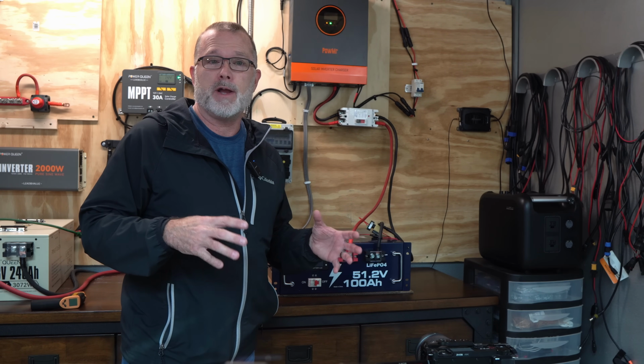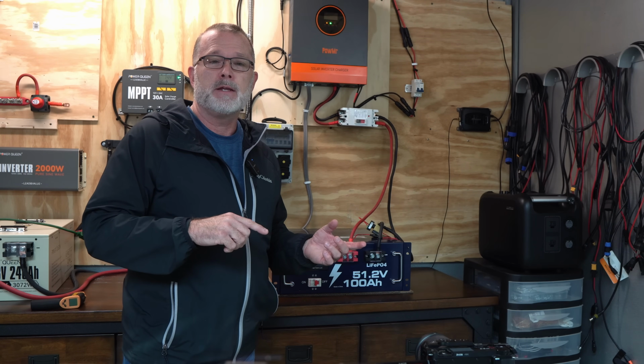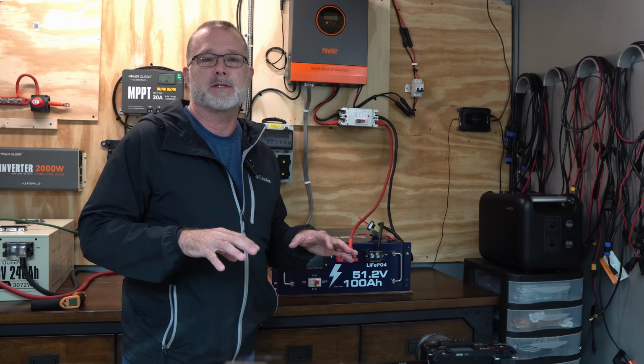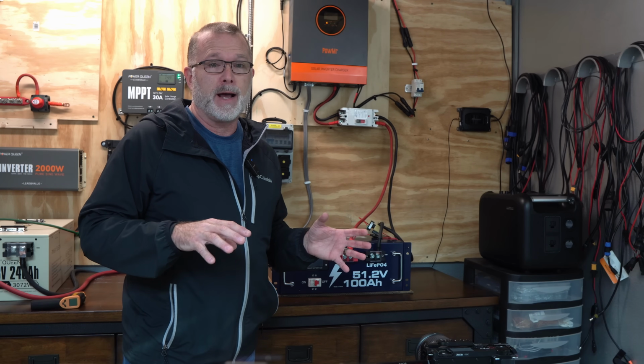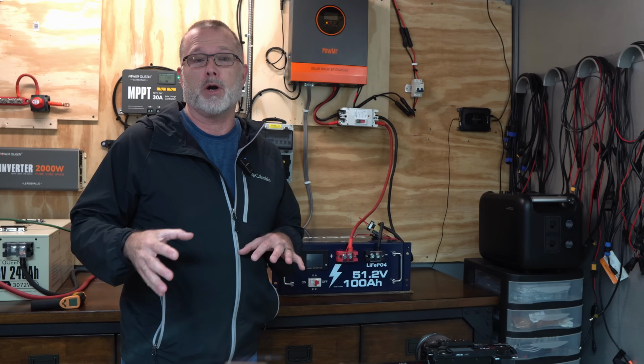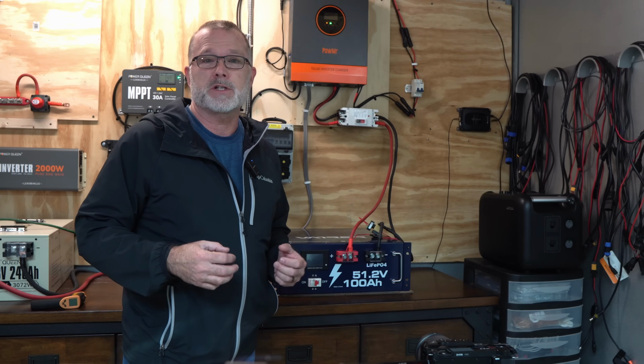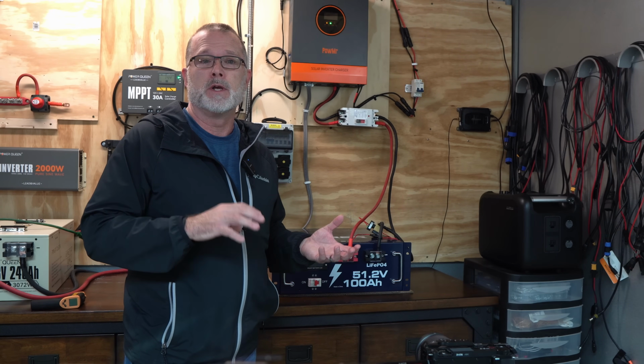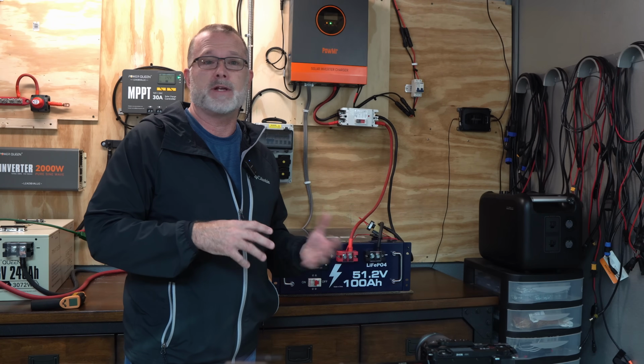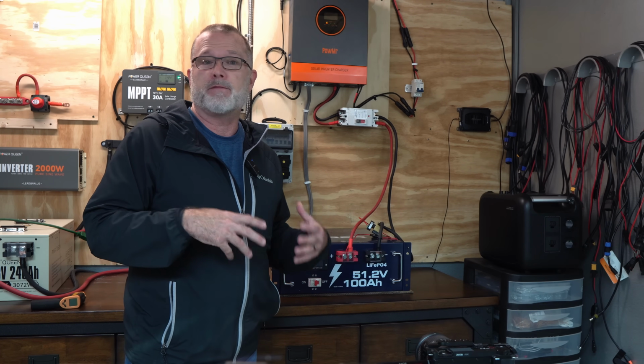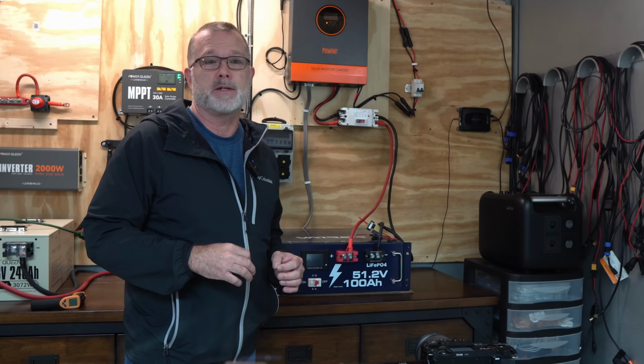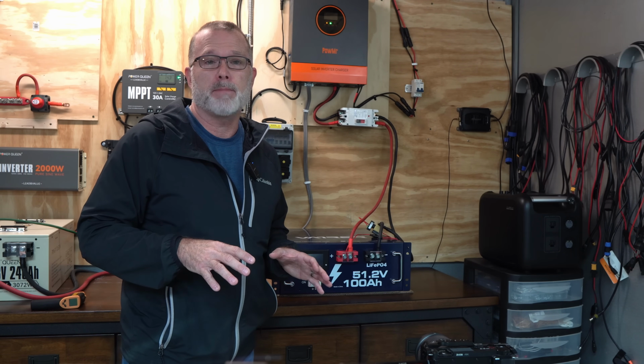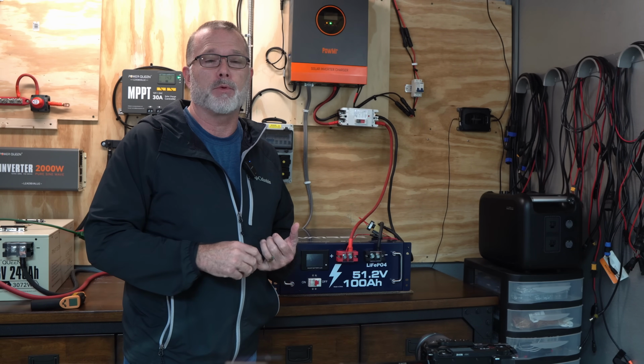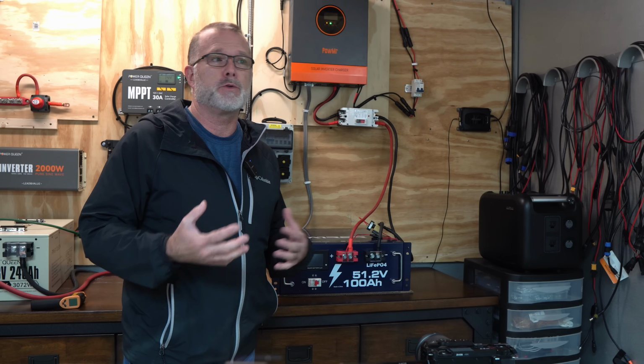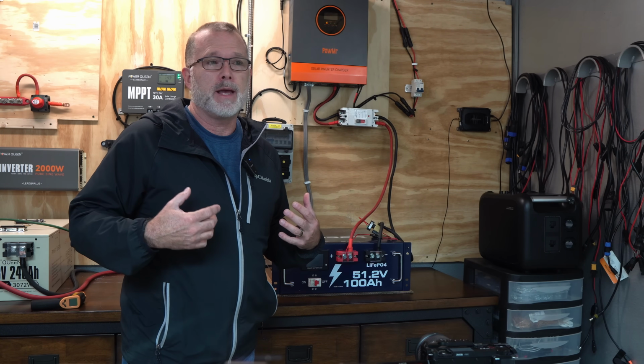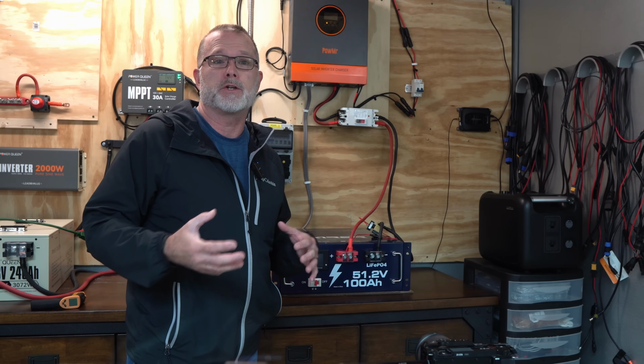In contrast, when you have multiple batteries connected in series, that natural equalization process does not happen. And in fact, they will tend to naturally drift apart just due to the inevitable slight differences in resistance that occurs in the cabling and the connectors and even the batteries themselves. Maybe if they're experiencing slight differences in operating temperatures.